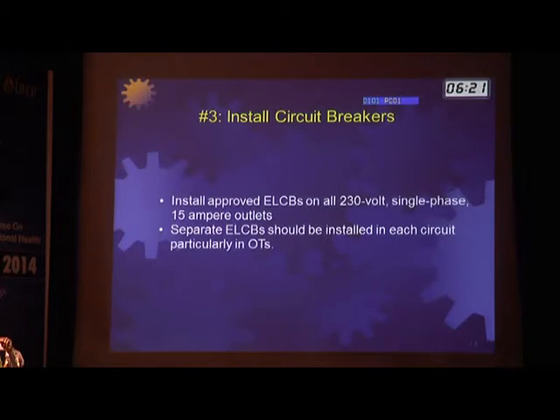Have separate ELCBs in the OTs. If you are going to have ELCBs, please have separate ones, because there might be some life-saving equipment on another line, and because of a fault in one line, the ELCB will switch off and the whole OT will go off, and you'll land into trouble, losing the patient.